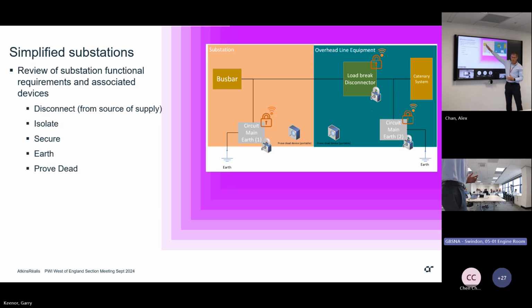Basically, we need to be able to isolate the busbar from the catenary and make the busbar safe to work on while you're still running trains. Similarly, you might want to keep the busbar live but be working on parts of the catenary. So you need to be able to earth up the catenary, keep the busbar live, make them secure, and be able to do the tests.